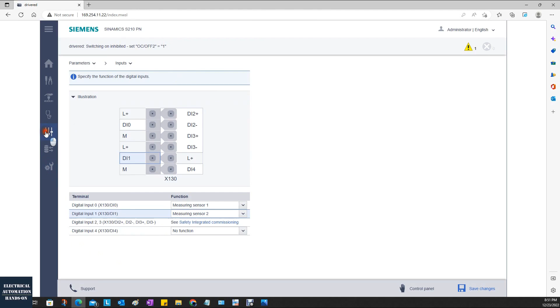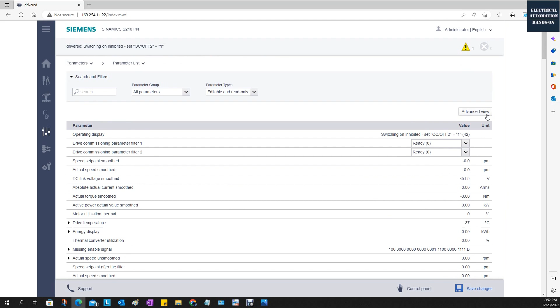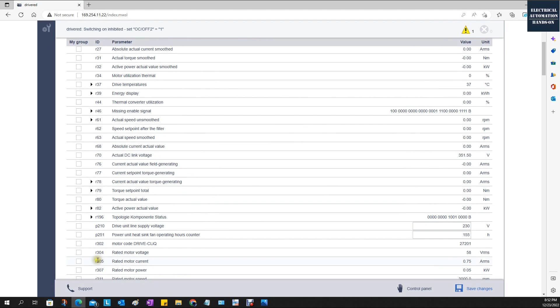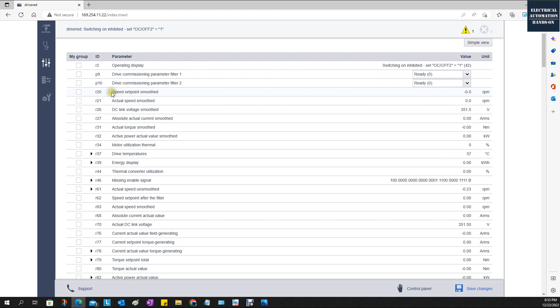And then let's go to the parameter list. Firstly, reading the servo motor from the motor to this servo drive is totally automatic. Basically, all those parameters automatically identify the servo motor it is connected to. So we will see all those parameters here. Also, you can click this advanced view. From this ID, you will see the number showing here. For example, this active power actual value. All the r parameters are reading parameters, read only. And all the setting parameters are p parameters.